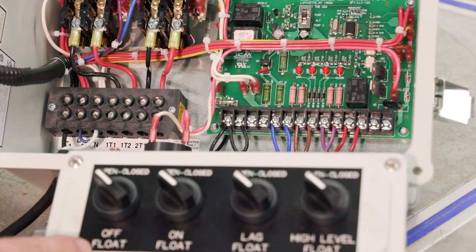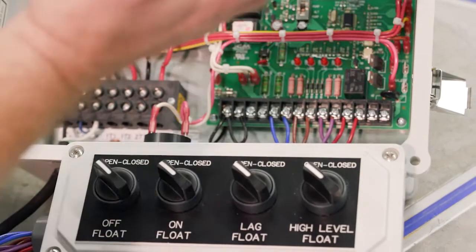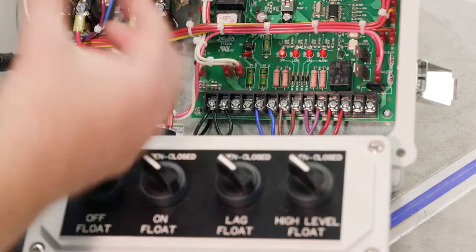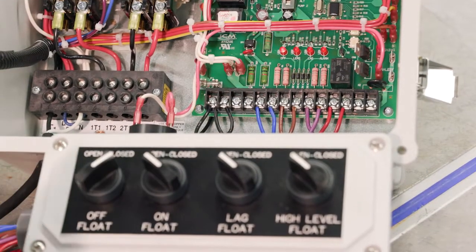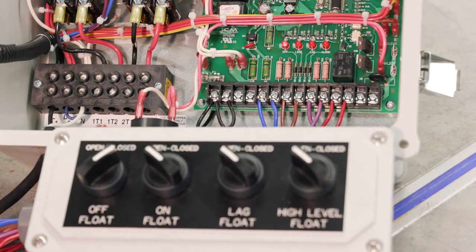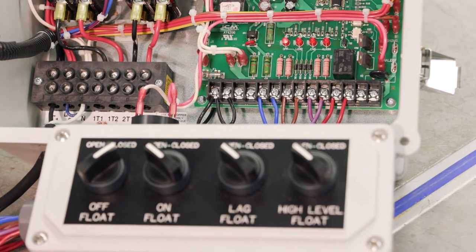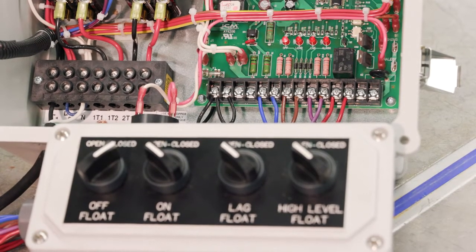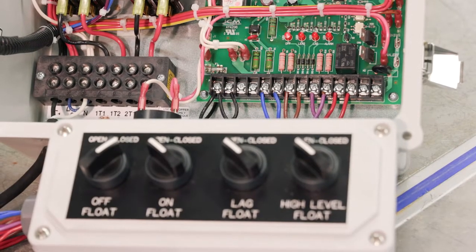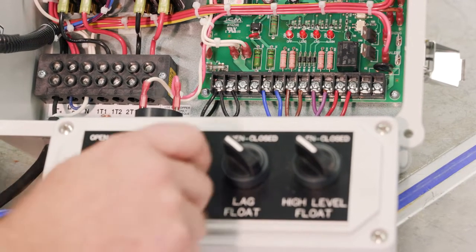So the lowest float is the off float, and the water level rises and turns that on basically, closes those contacts, which again, you can use a jumper. So other than the light going on, the off LED, then nothing else happens, which is what it's supposed to do. So the water keeps rising, it gets to the second float, which is the on float.